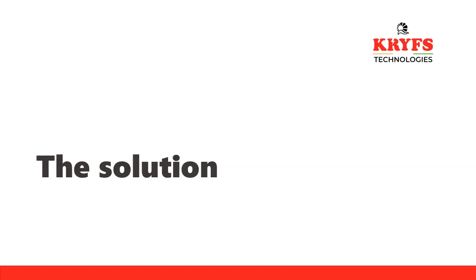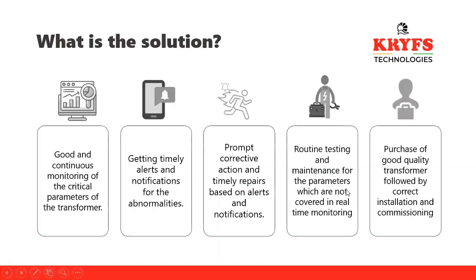Often many of the transformers fail within the first 5 years. That can be because of manufacturing defects, but after that, because of improper maintenance, the transformers fail too early. The solution can be good and continuous monitoring of critical parameters of the transformer. If there is a manufacturing defect in a new or an old transformer, because of continuous monitoring, you will definitely get to know in the initial period only.